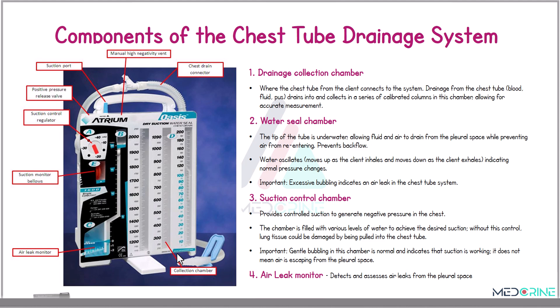Another important component is the air leak monitor, which detects and assesses for air leaks from the pleural space. Looking at this image, starting from the bottom right we have the collection chamber, then the air leak monitor labeled C, a suction monitor bellow, a suction control regulator, a positive pressure release valve which is a safety valve, the suction port on top, a manual high negativity vent, and a chest drain connector to the patient.